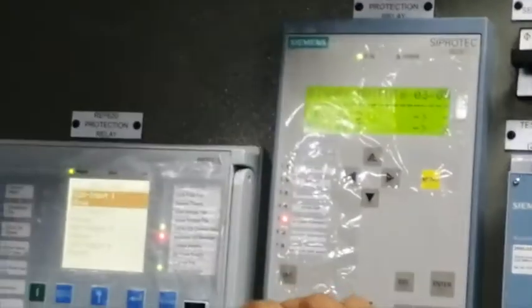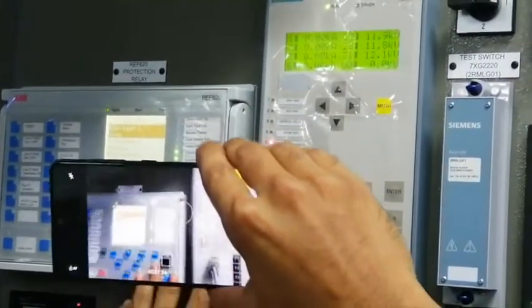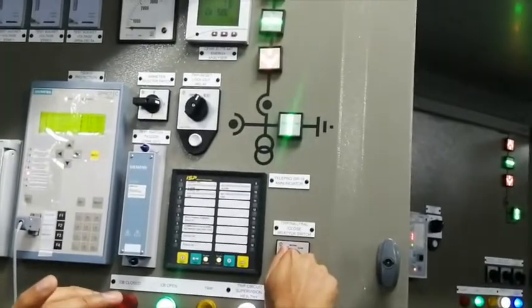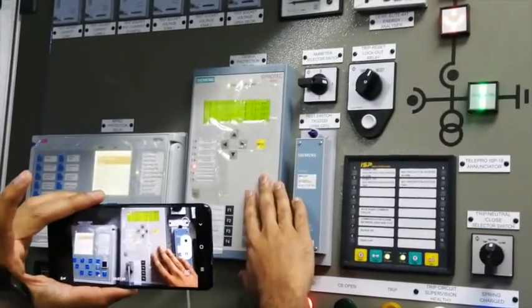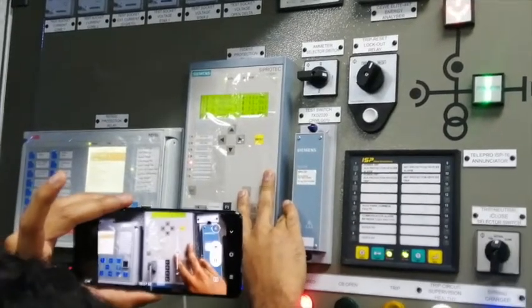All other conditions need to be satisfied. We simulated the VT connection to provide line-side voltage. After turning on the breaker to provide line voltage, everything is good — no alarms, no errors, all LEDs are green. The 132kV circuit breaker is already closed, so we are allowed to close the 11kV breaker. We close it, and the breaker closes successfully. This confirms we are receiving the 11kV CB close permission from the 132kV side.